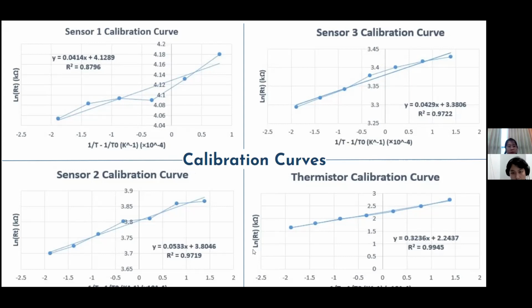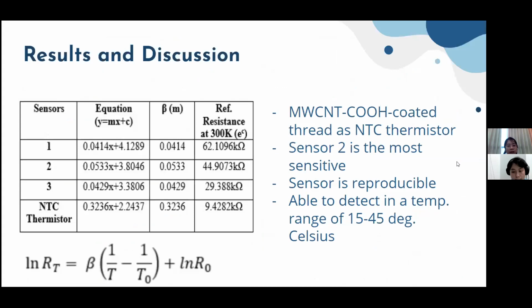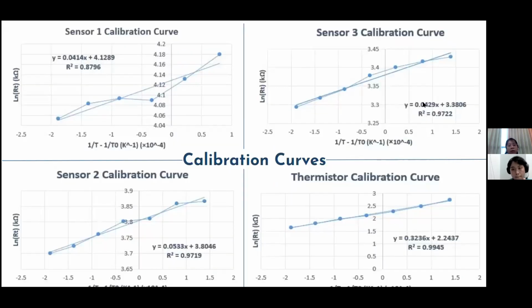Next is sensor 2, because as we can compare, it is 0.0533 compared to sensor 3 and sensor 1 - this has the bigger value, meaning it has the best sensitivity among these three sensors. Next is sensor 3, and the third one is sensor 1. So that's the calibration curves.